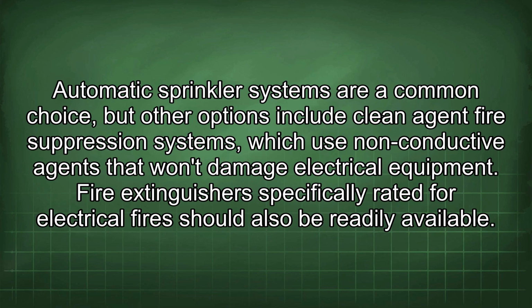Automatic sprinkler systems are a common choice, but other options include clean agent fire suppression systems, which use non-conductive agents that won't damage electrical equipment. Fire extinguishers specifically rated for electrical fires should also be readily available.